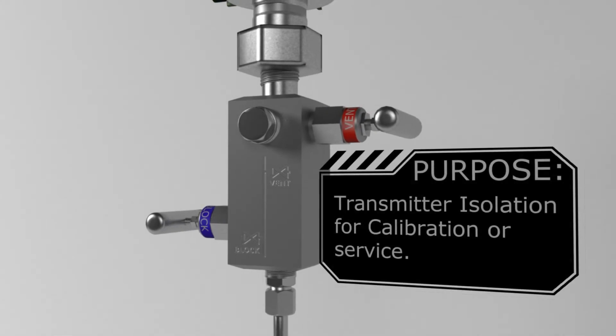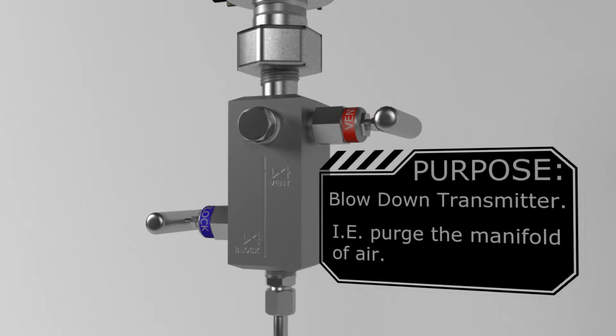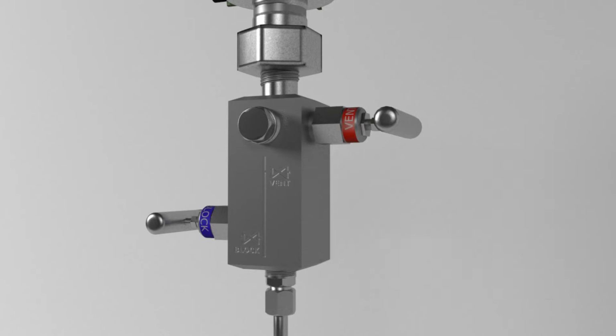The purpose of a pressure manifold is to isolate the transmitter in order to perform a calibration or to service the transmitter. It is also used to blow down the transmitter, meaning to let all of the air out of the manifold while the transmitter is online. This ensures an accurate and stable reading.